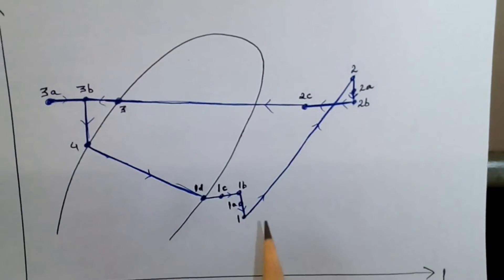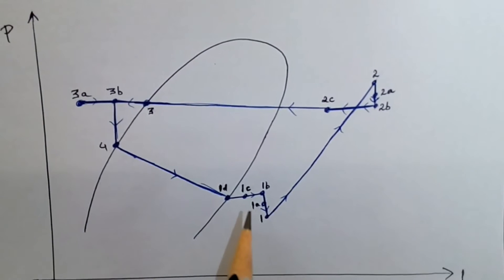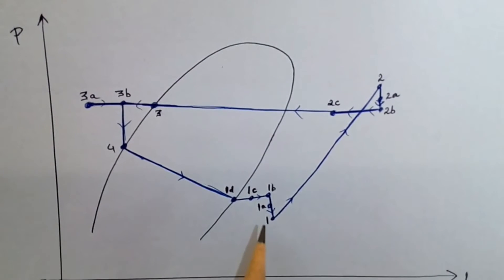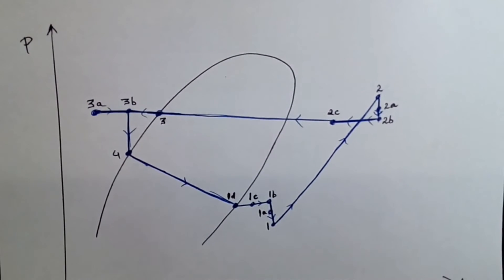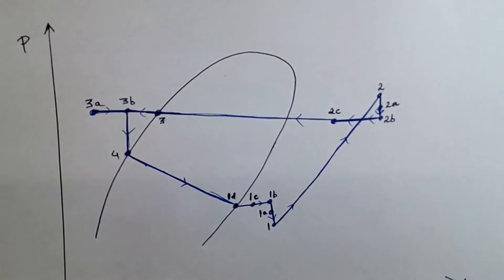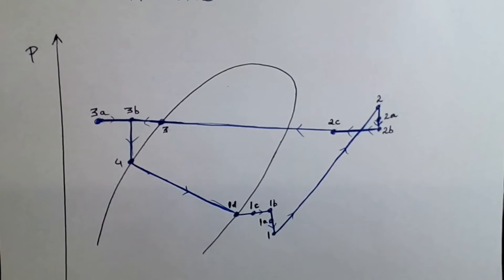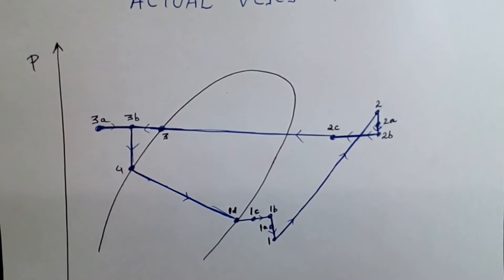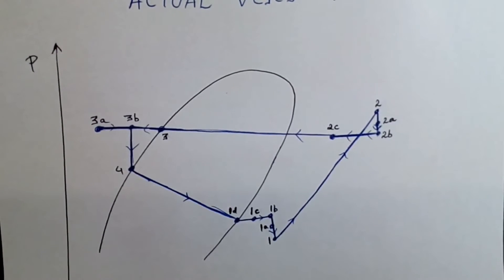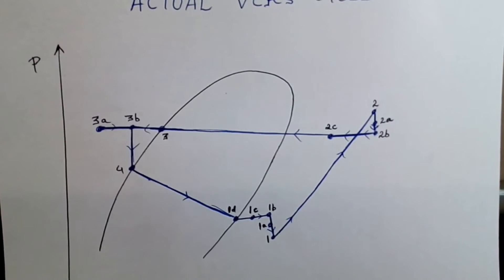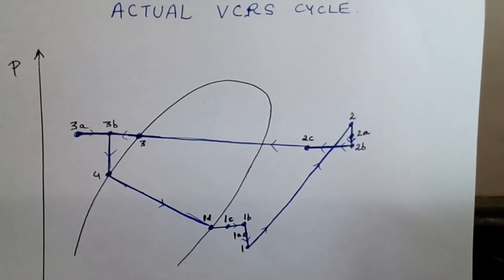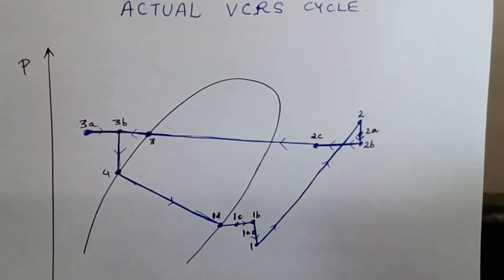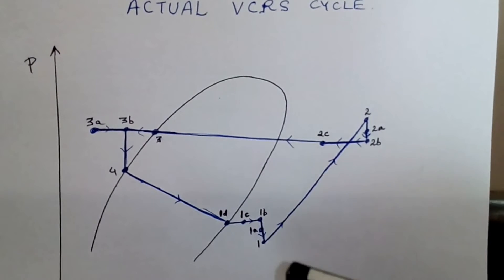From 1a to 1 there is a further pressure drop. When the vapor refrigerant enters the inlet valve of the compressor, there is a pressure drop due to the wire-drawing effect, also called the throttling effect.